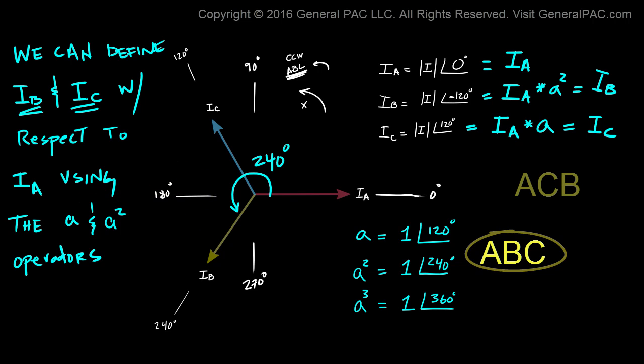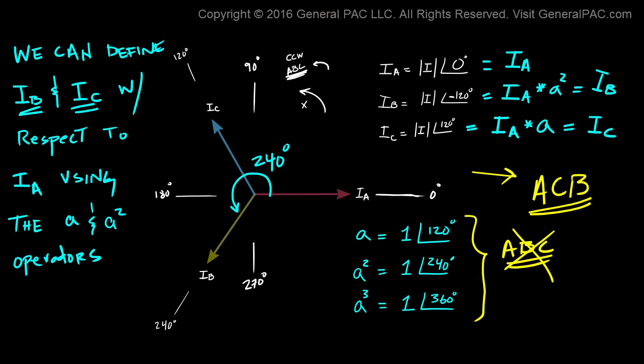But if you have an ACB phase sequence, these A operators are going to be different. So let's just go over that really quickly. Now we're not talking about ABC anymore. Now we're talking about ACB. What would we have to do with this phasor diagram? Well, to be an ACB phase sequence, we have to change that to IC, and then we have to change that to IB. Now this is an ACB phase sequence.